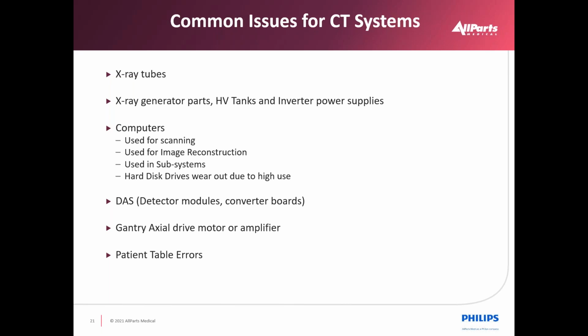And then we have to deal with the gantry, the axial drive motor spinning, whether it's integrated to the gantry or a separate motor and belt driven, and the amplifier that drives that. And then we have patient table errors that will be part of the challenge as well. In a lot of cases, it's the tape switches, because as they move patients in and out on gurneys, they will tear a tape switch, and that interference switch will then be open, and the table won't be able to run. The other is the element that drives the table in and out of the gantry that is being used quite a bit. And so over time, we'll see challenges with bearings or motor drive circuits for the table as well.